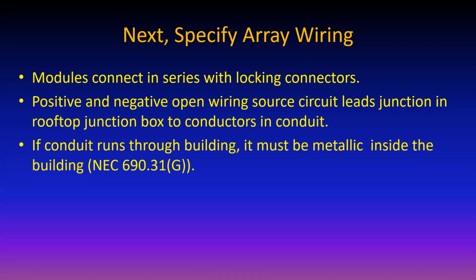Anything carrying DC through a building is supposed to be metallic. There are now some reasons why it can be otherwise. With rapid shutdown, it's now not quite as essential to have metallic conduit run. You can run PVC. Generally, you can convince the local jurisdiction that PVC is a better deal. Sometimes it's not. Sometimes it doesn't hold up nearly as well in an attic as EMT, but in a saltwater environment, there are certain environments where metallic conduit doesn't hold up very well, and PVC is a whole lot better. So talk to the local authorities on that one.